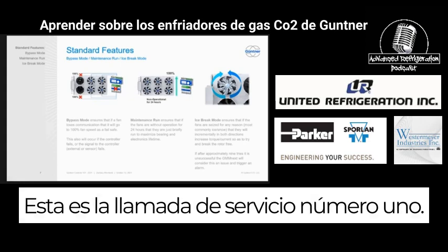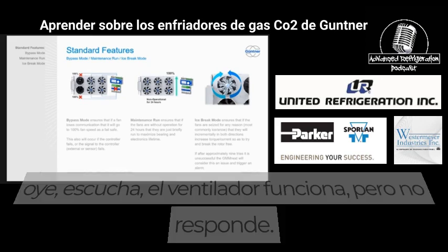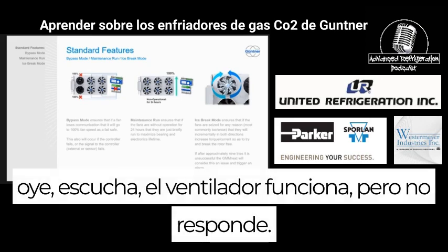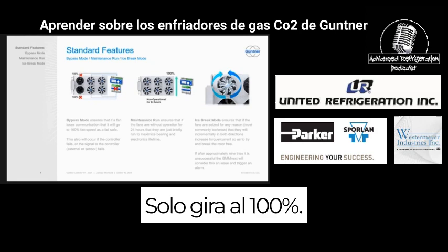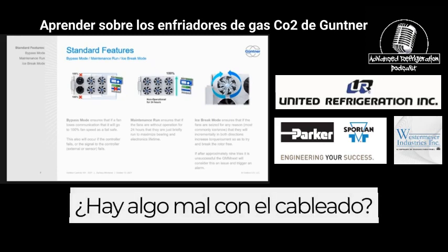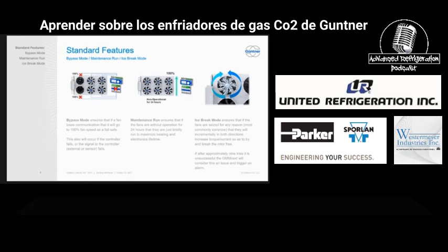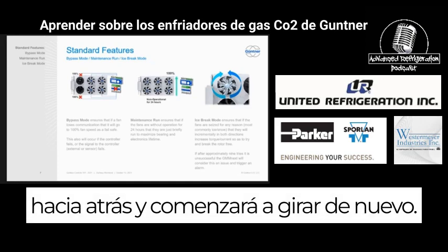So this right here is the number one service call I get. I'll get a guy in the field calling me, saying, hey, listen, the fan is working, but it's not responding. It's only spinning at 100%. To which I'll say, you know what? Check the wiring. Is there something wrong with the wiring? Is there a loose wire? And sometimes a loose wire will bring it back and it'll start spinning again.